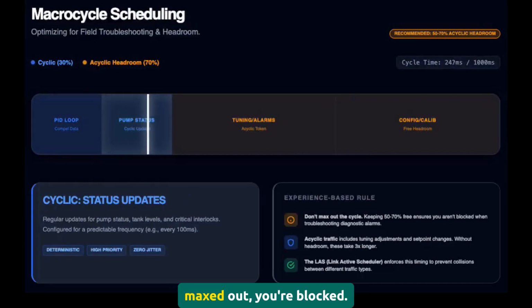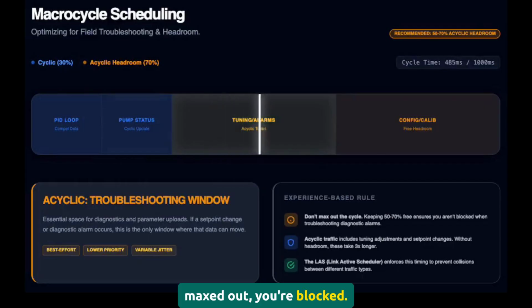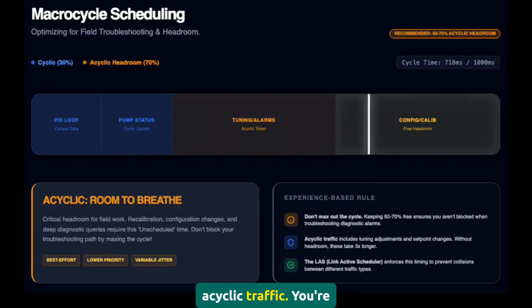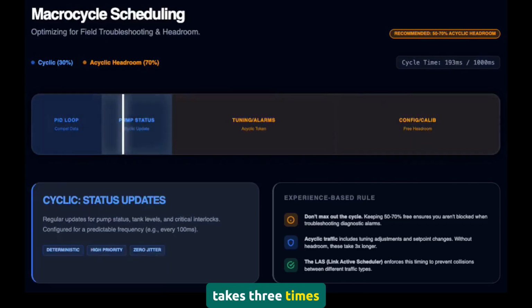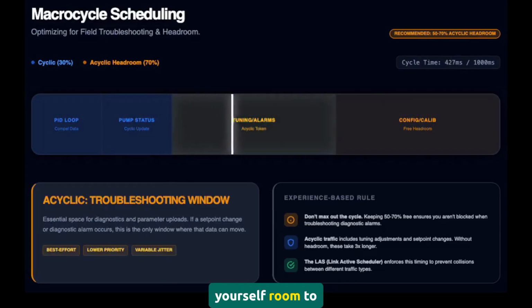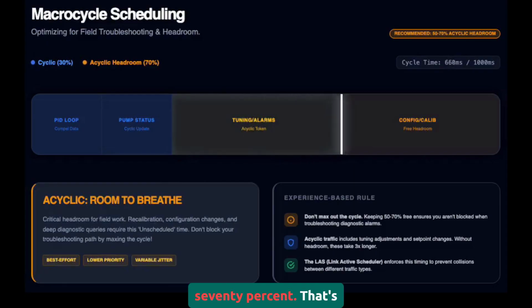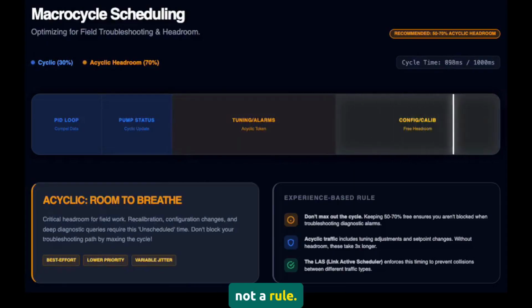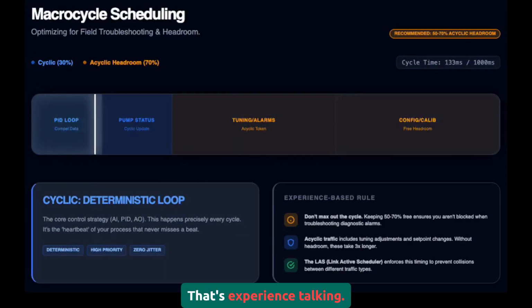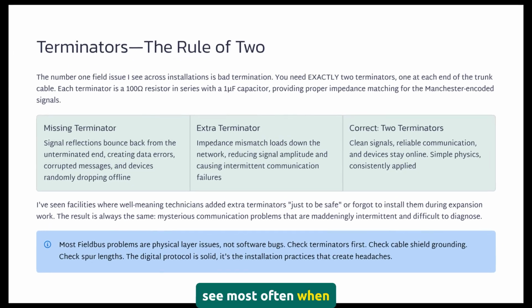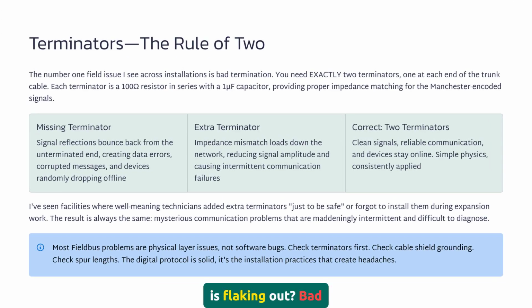If your cycle is maxed out, you're blocked. You can't send that acyclic traffic. You're stuck waiting for the next cycle. Suddenly your troubleshooting takes 3 times as long. Leave yourself room to breathe. 50 to 70%. That's not a rule. That's experience talking. You know what I see most often when a Foundation Fieldbus network is flaking out?